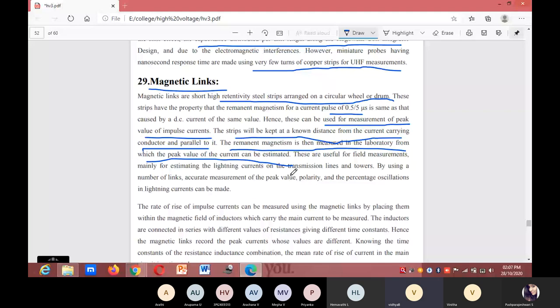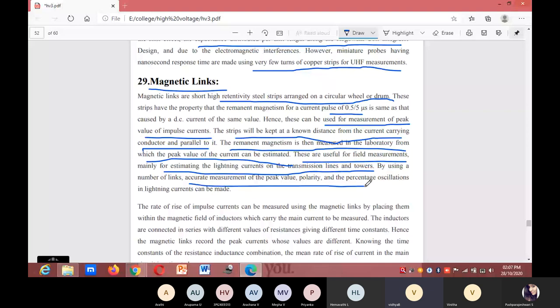These are useful for field measurements and mainly for estimating the lightning currents on transmission lines and towers. By using a number of links, accurate measurement of peak value, polarity, and the percentage oscillation in lightning current can be made.